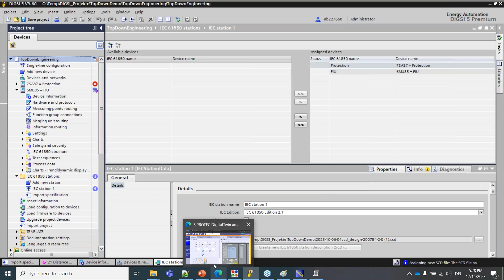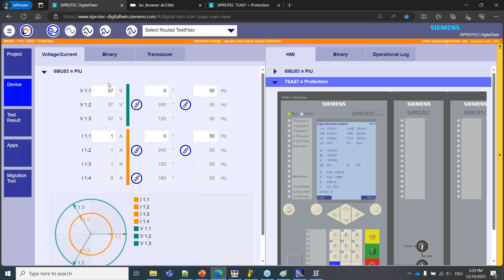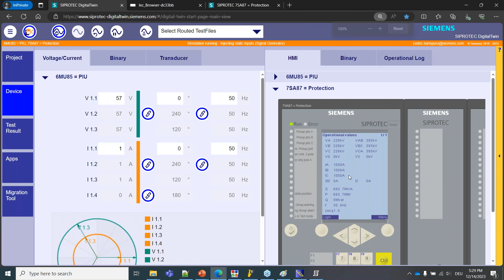And here I'm currently simulating two devices, our merging unit we've been talking about at the beginning, and the protection device. Both devices are running at the same time. And if I inject voltages and currents at the merging unit that are then transmitted via sampled values to the protection device, you see that the values are received at the protection device. Here, this is the front display of our 7SA87, where we have the navigation possibilities that you know from the real device.